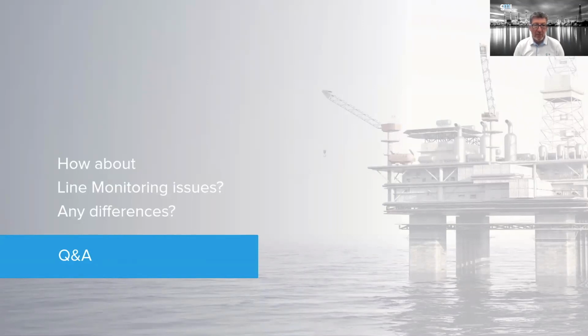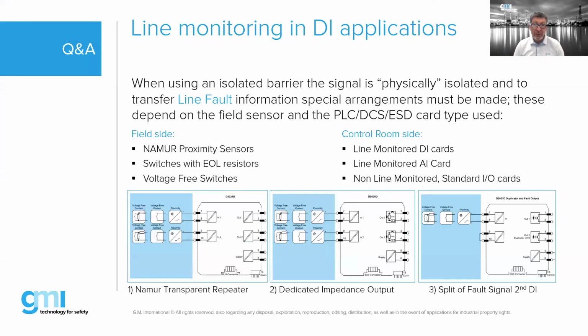Well, we have a question about line monitoring. I'll try to make this very brief. When you're using an isolated barrier, you're basically isolated. So you put in a wall, a partition between your signal in the field and the control room. That has to go through the transformer. So the transformer, as we said earlier, allows you to transfer it if you provide a specific transformer to do that. You have to do the same for the line monitoring. So they are specifically designed, isolated barriers to handle line monitoring, whether it's DI or DO.